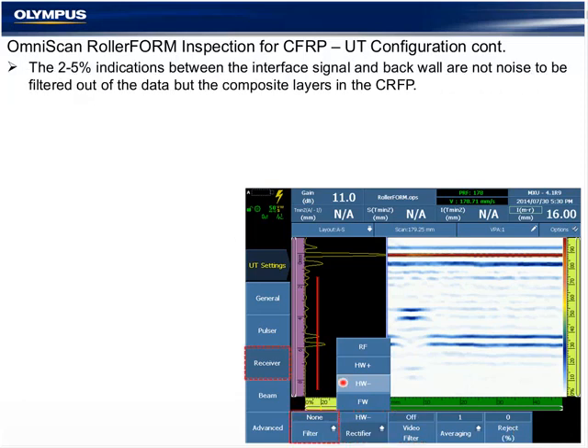And filter selection. The short version is to use the filter that works best. When no filter is selected, we are benefiting from the full bandwidth of the probe frequency, and as soon as we select a filter, it's going to crop off portions of that. Use what works best, but don't be surprised if best results are achieved with no filter selected at all.